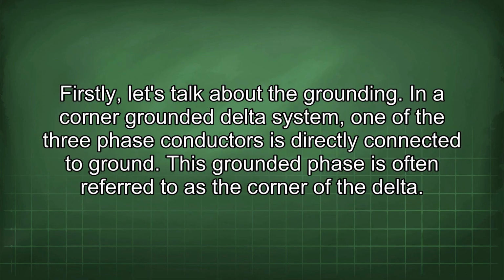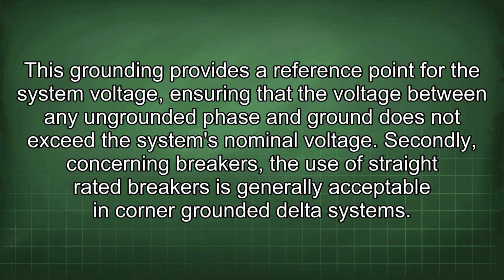Firstly, let's talk about the grounding. In a corner-grounded delta system, one of the three-phase conductors is directly connected to ground. This grounded phase is often referred to as the corner of the delta. This grounding provides a reference point for the system voltage, ensuring that the voltage between any ungrounded phase and ground does not exceed the system's nominal voltage.